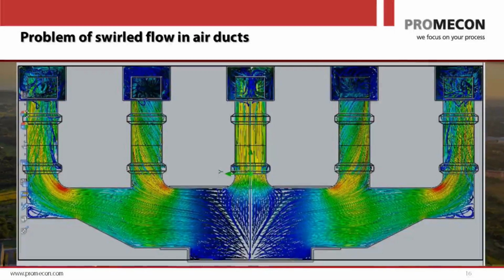And that is another very big advantage of our measurement, because you never know how much swirl you have. It does not come necessarily from a fan upstream. The swirl simply comes by the fact that air ducts turn in different dimensions. They turn up, they turn sideways, and therefore you get these movements of air, and it's usually very hard to stop them. You have to put in a honeycomb, a flow straightener, that costs you a lot of pressure drop. Our measurement is not sensitive to this. It only measures the flow in the direction of the duct, and therefore our measured airflow is really equal to the air mass flow.